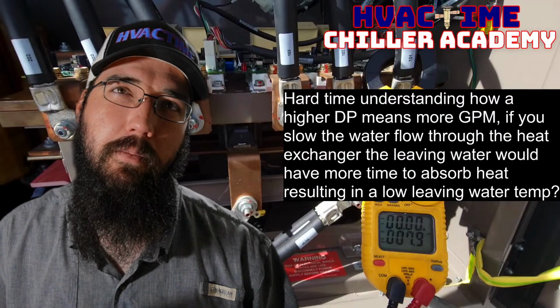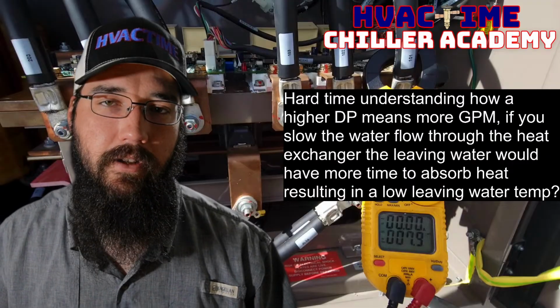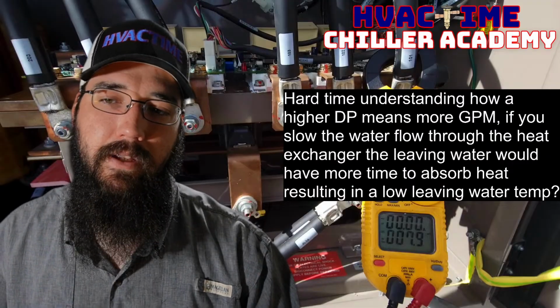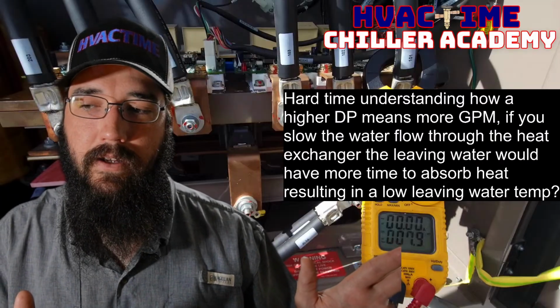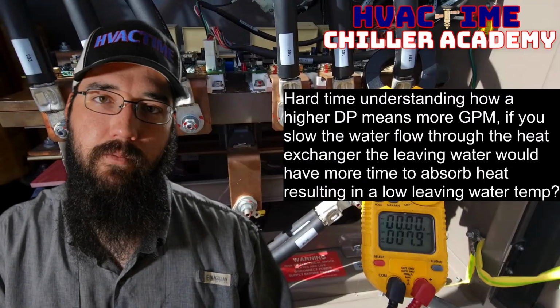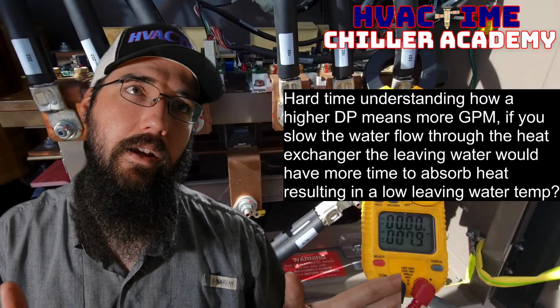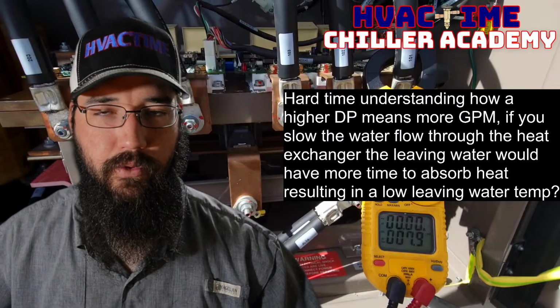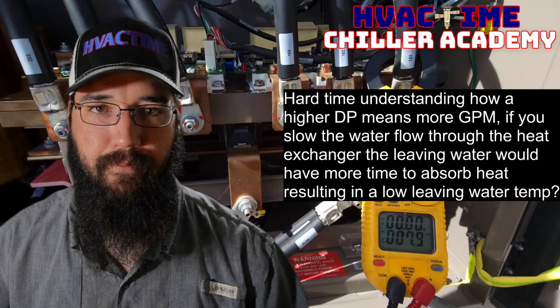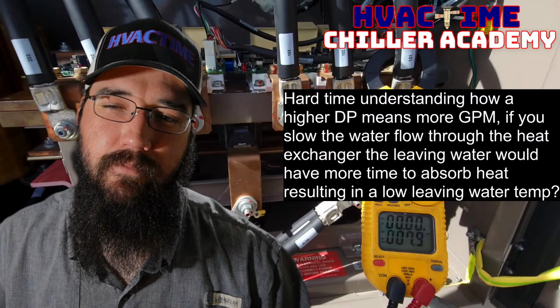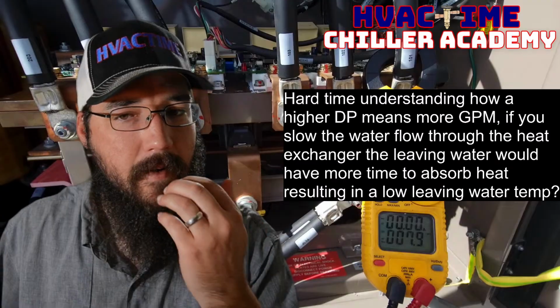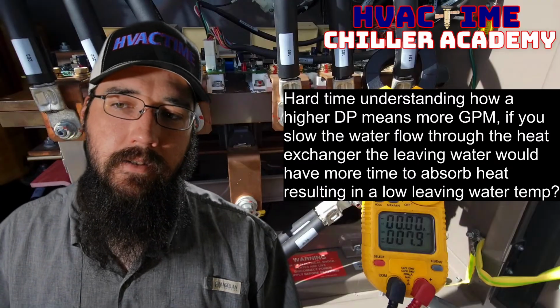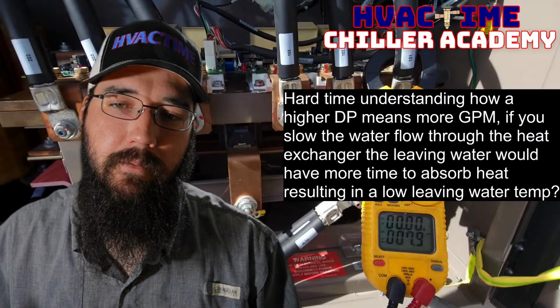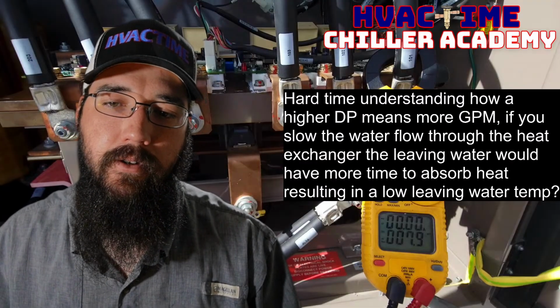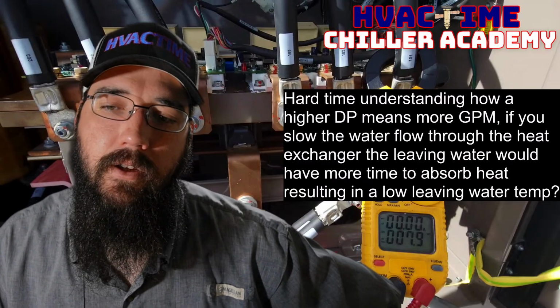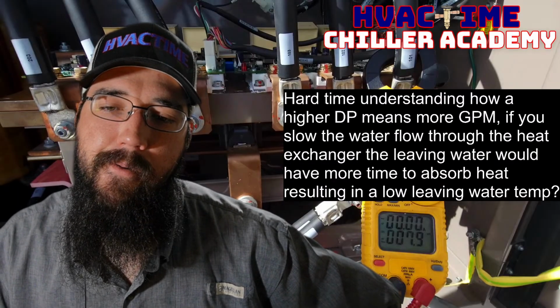Hopefully my phrasing there is helping bring some clarity to this, and just the fact that we have DP for GPM and actual temperature difference, that there's a separation between those two. They're not the same. Let's see, do I want to hit anything else on that topic? Higher DP means more GPM. If you slow the water through the heat exchanger, the leaving water will have more time to absorb heat. Yeah, no, I think it's good.